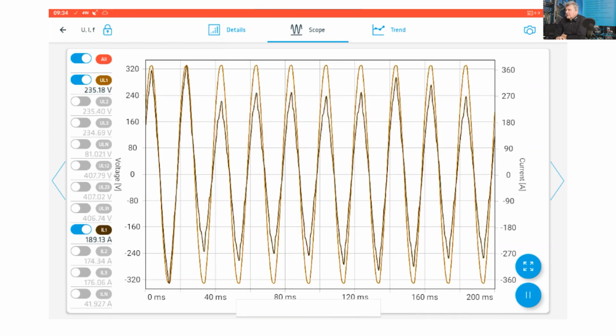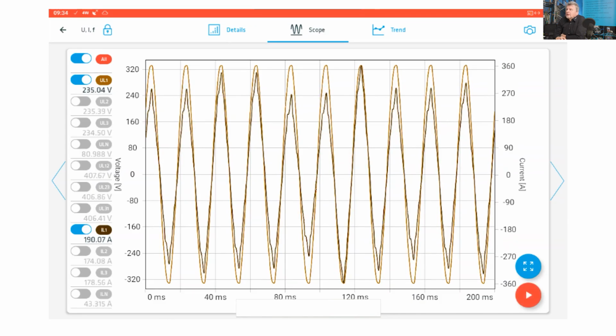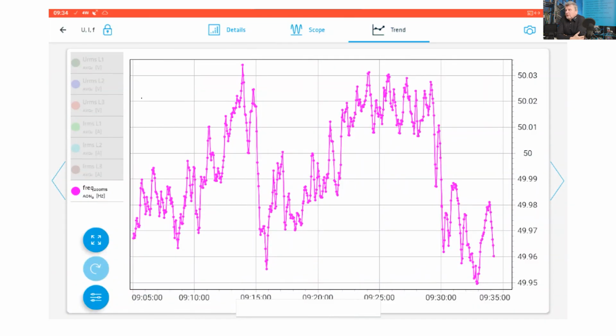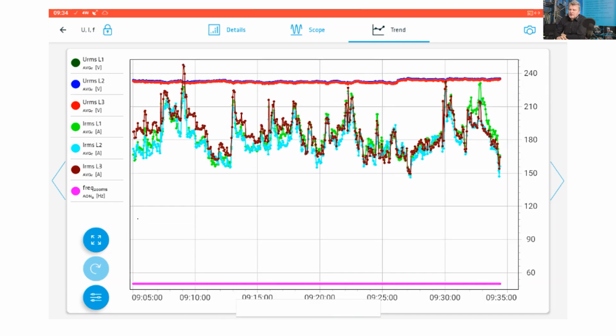For further analysis, you can stop the scope view and monitor with the cursor to see specific anomalies which are happening here. Under trend view, normally you monitor preselected values. To enable smooth and easy operation, we specified for each connection a so-called default view. For each measurement, the default view specifies what will be visible. For example, for voltage, current, and frequency, the default view automatically selects voltage, current, and frequency. You can select up to 8 different parameters.